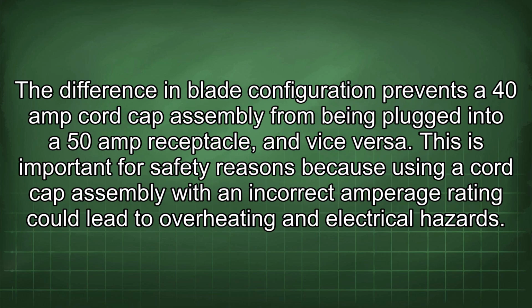The difference in blade configuration prevents a 40 amp cord cap assembly from being plugged into a 50 amp receptacle, and vice versa. This is important for safety reasons because using a cord cap assembly with an incorrect amperage rating could lead to overheating and electrical hazards.